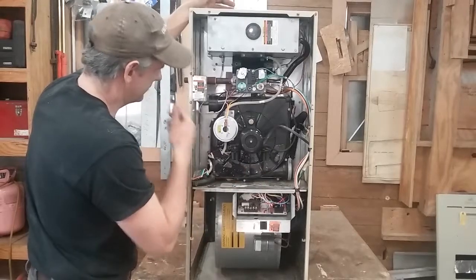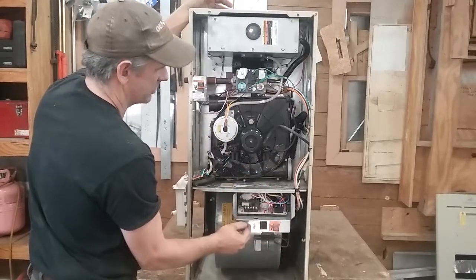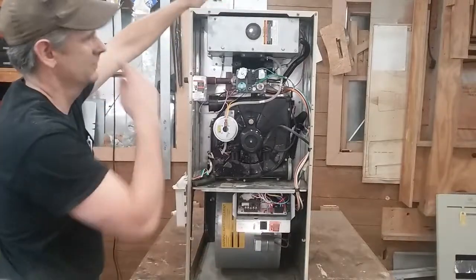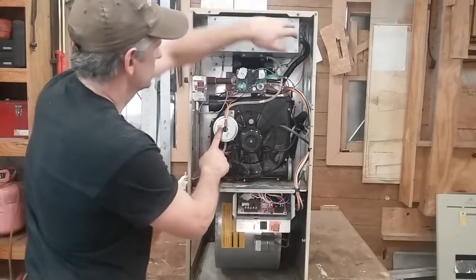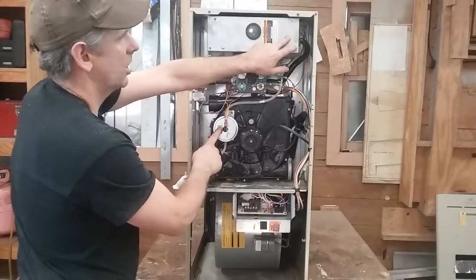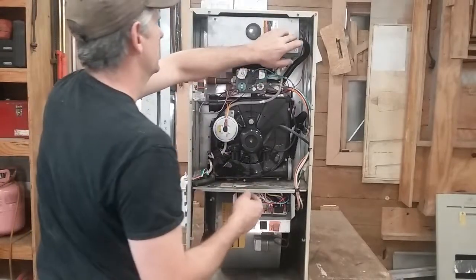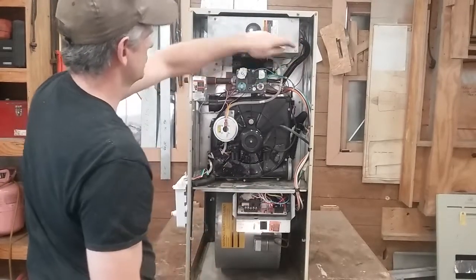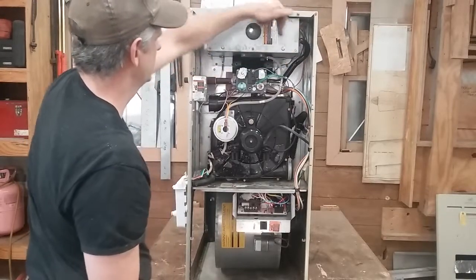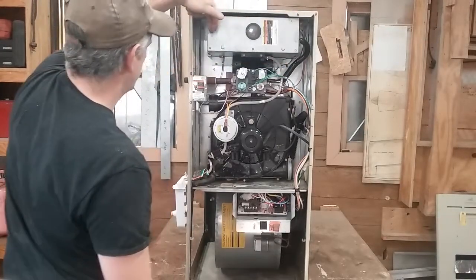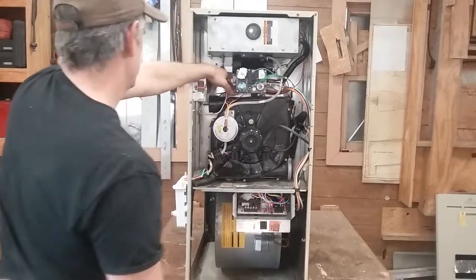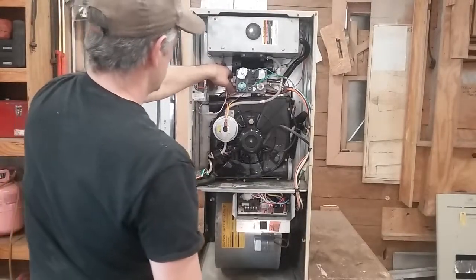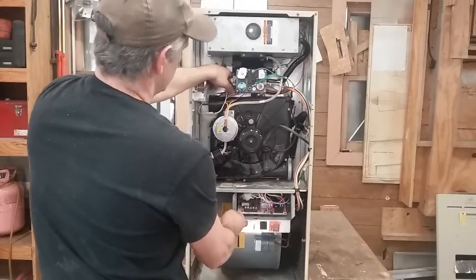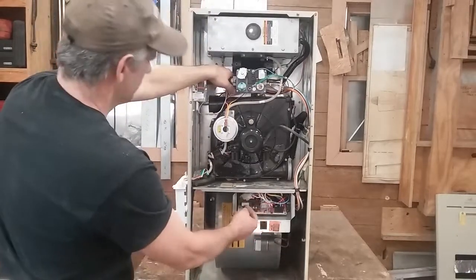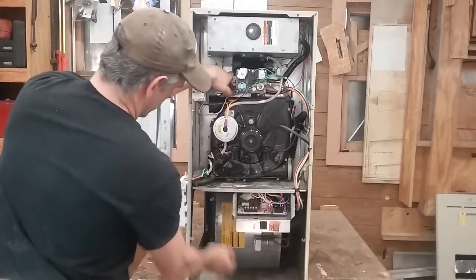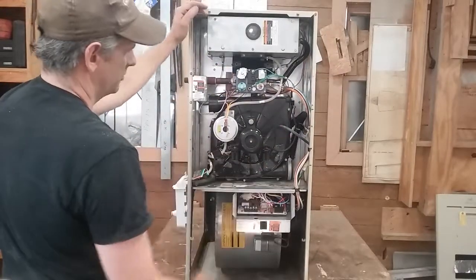Once the heat exchanger's got a little bit of vacuum on it, it closes the vacuum switch. A timer starts. After so much time, if the vacuum switch stays closed, the igniter over here comes on, gets hot after so many seconds. Then the gas valve opens. When the gas valve opens, the gas hits the igniter, the flame lights up, travels over here to the flame sensor. Once the control board senses the flame through the flame sensor, another timer starts. So many seconds later, the blower kicks on, blows hot air out the top of the furnace.